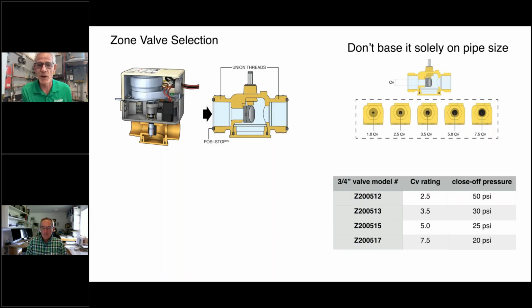But what's the reason for the small hole, Siggy? Well, you see this chart down at the bottom. Basically, it's a trade-off. The smaller the CV rating, the higher the close-off pressure rating. So close-off pressure is the maximum pressure that the valve can close against. And it stands to reason that that spring in that assembly inside the zone valve can only create so much force or torque on the shaft. So as the size of the orifice that the flow goes through increases, pressure times area equals force. So as that orifice gets larger, and you can see here the CV rating goes up, which means you have less pressure drop through the valve, but the trade-off is it's going to have reduced close-off pressure.